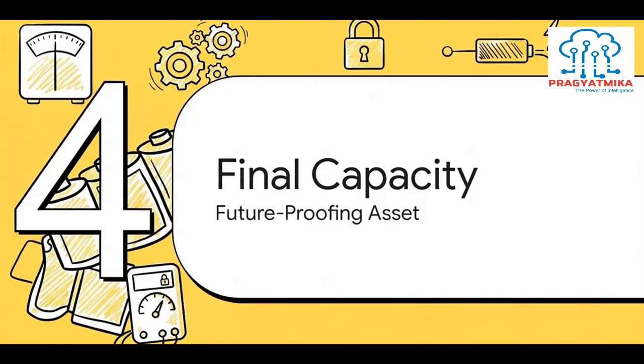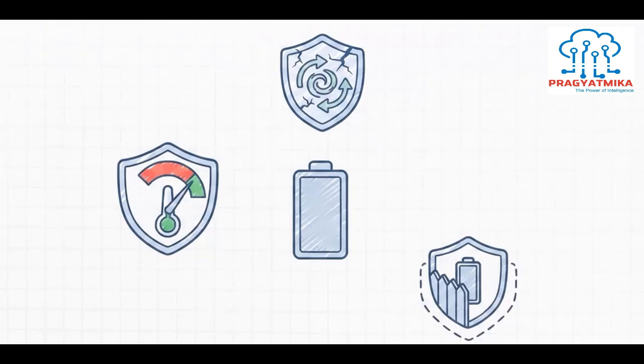Step 3, final capacity, future-proofing the asset. This is where we finally lock in the numbers. To protect this asset for the long haul, you've got to bake in safety margins. You need buffers for inevitable battery degradation down to an 80% state of health, and you have to include temperature derating for hot climates. If you are installing a system in an incredibly hot location, say 45 degrees Celsius ambient temperature, the internal resistance increases. The battery physically cannot hold or deliver what it does in a perfectly climate-controlled 25-degree lab setting. Adding a 10 to 20% safety margin is what ensures true long-term reliability.